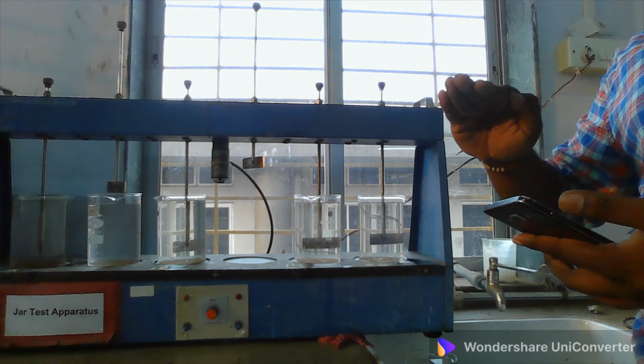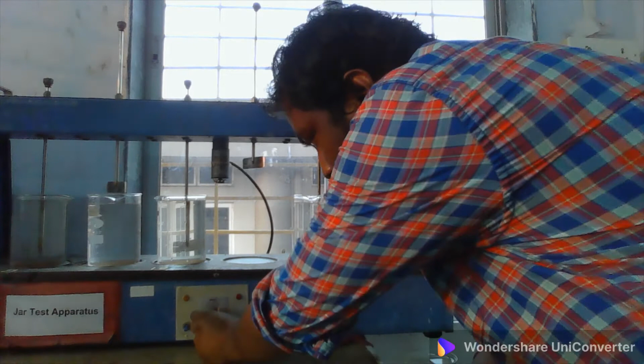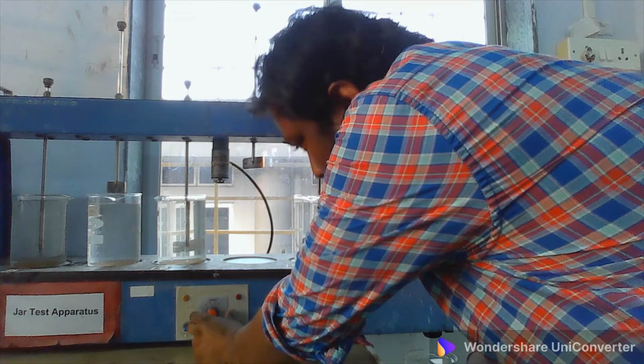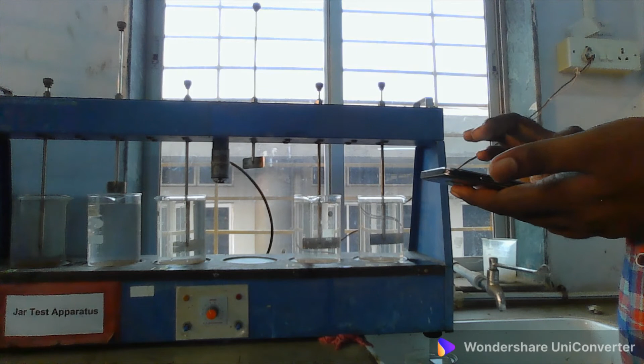Now I am going to set the RPM. We have to set 25 to 35 RPM. I'm going to set 30 RPM here, and then I will set 15 minutes on my mobile, and now I'm going to start the switch. After 15 minutes I'm going to close the apparatus, and I'm going to observe the floc settlement for 30 minutes, and then I'm going to take the reading.